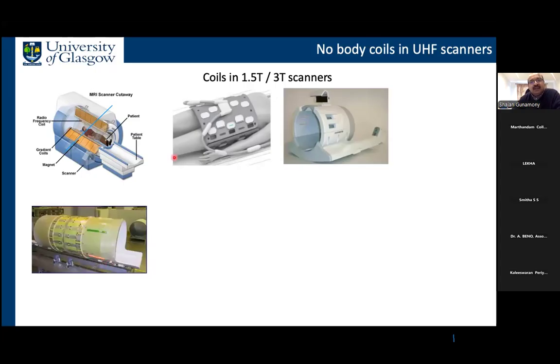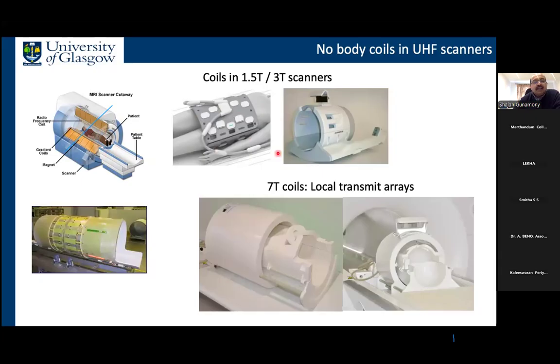Okay, so here is something I showed in the first topic. In a clinical scanner, you have a transmit coil, and then you have separate receive coils. In an ultra-high field scanner, you cannot have a single transmit coil for the reasons I explained just now, because you need control over the amplitude and phase to each of these coil elements.